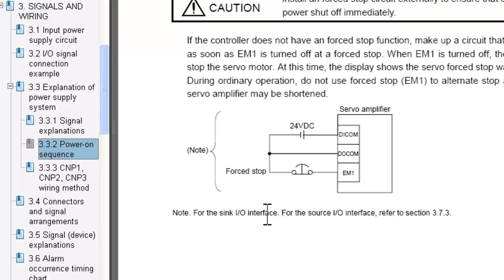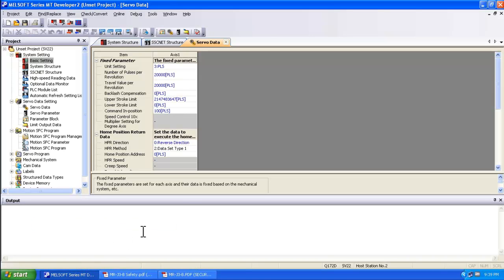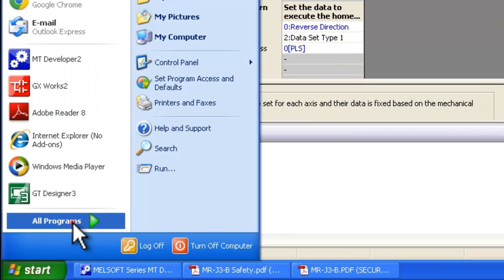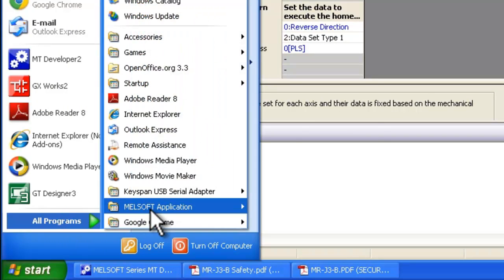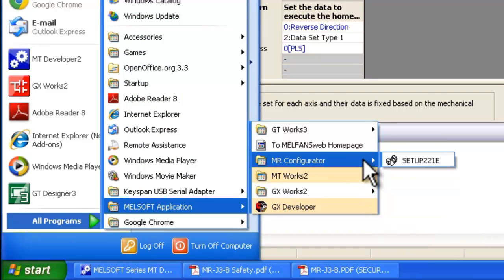This is also available in any of the other Mitsubishi servo amplifier manuals, though the section will obviously be different. Now let me run through how you can disable the E6 warning through software. I'm assuming everyone is using MT Developer 2 or MT Works 2, accessed through Start Menu > All Programs > MelSoft Application > MT Works 2. I'm also assuming everyone has MR Configurator on their computer, which is necessary to disable this through software. For J3, the software is setup 221E as shown here.